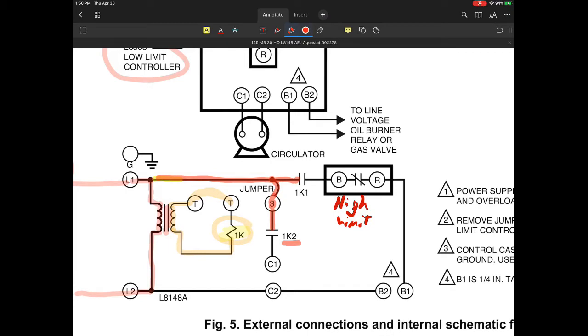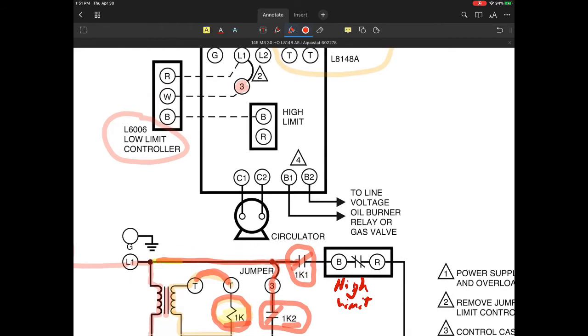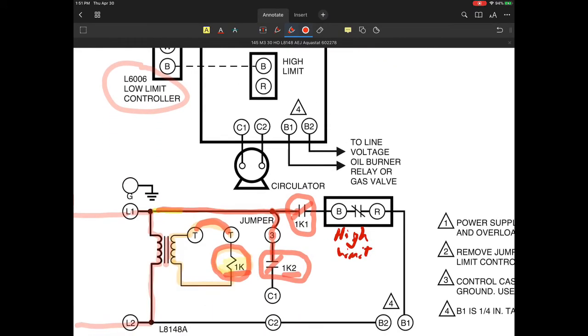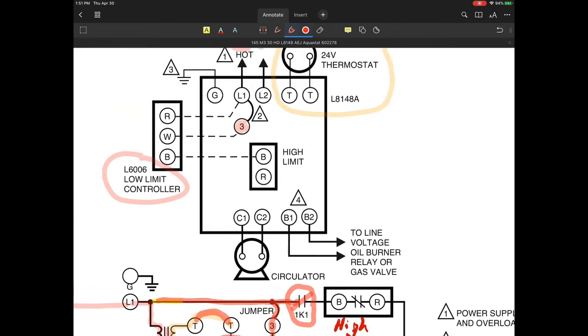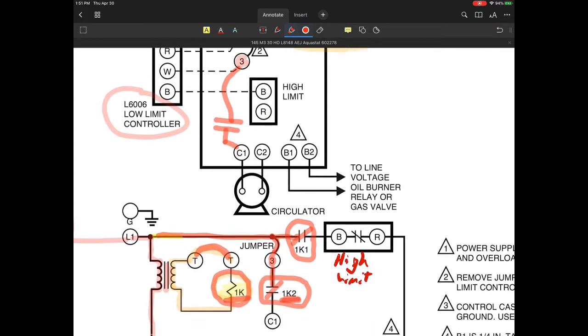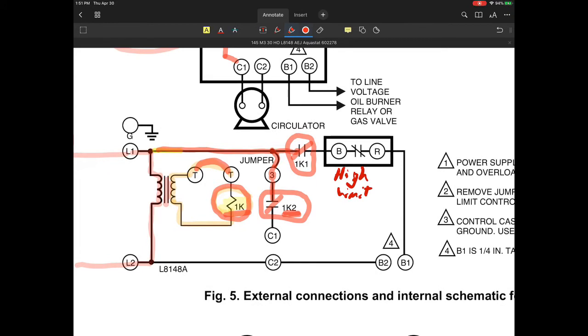Additionally, this device is now going to take that line voltage with that little jumper that went to terminal 3, and that's going to go to the 1K2 set of contacts. Both 1K1 and 1K2 are actually going to be energized, or let's say closed, upon energization of the 1K relay. So as soon as there is this demand, this contact closure, both of these relays should close. As I had mentioned earlier, you've got a C1 terminal. That's going through the 1K2 relay, the second set of contacts on the relay, going from here directly through to another set of contacts, which is now going to go to C1. That's exactly how they're identifying this and showing that here.